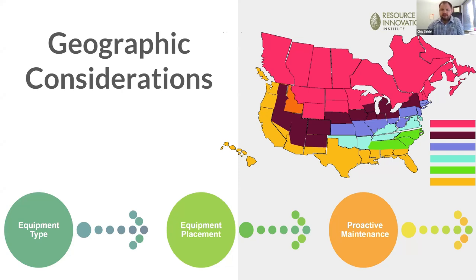Just noticing this slide, I don't think it pulled through some of the lettering on the map, but you can tell by the different colors. These are different climatic regions, and the shading corresponds to the number of hours below a certain temperature, which corresponds to efficiency. So when you're looking at a chilled water system, if there's more time where it's below a certain temperature—here we use 35 degrees—then you're not going to need to run compressors to chill the water. You'll be able to utilize that outdoor energy and get significant benefits from an efficiency standpoint.